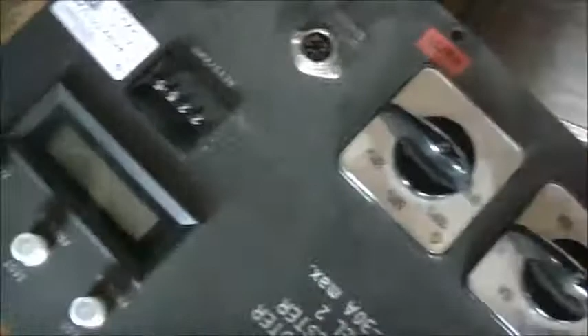Okay. Test counter. Count 10 disc revolutions, test duration typically 30 to 90 seconds. Meter error will be displayed on the test set at conclusion of the test. Use the percentage switch to select appropriate current levels. So this one. And it should be on this screen what the error is, and that will give you all of what you need to mathematically calculate the error percentage of what the meter should be. I'm pretty sure that's what this unit would do.